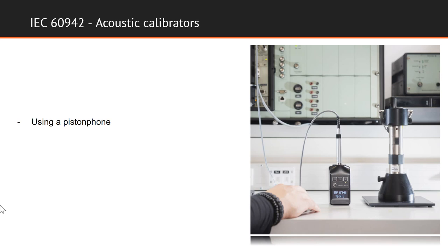The calibration is performed using a comparison method by utilizing the reference pistonphone as the standard comparative sound pressure level. The report of the calibration includes measurements of sound pressure level, frequency, and total distortion. If the instrument is equipped with an accessory barometer, this is checked at the current air pressure.